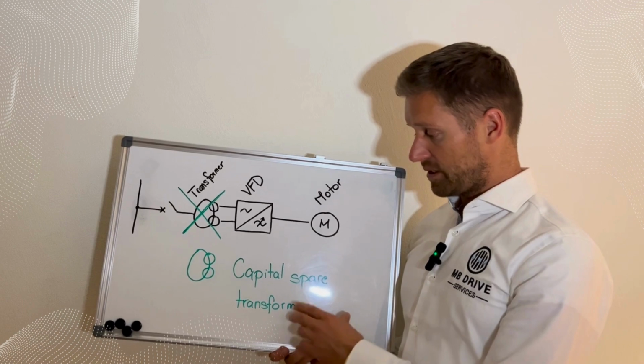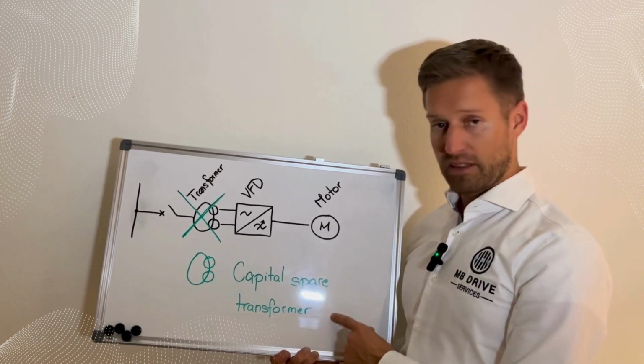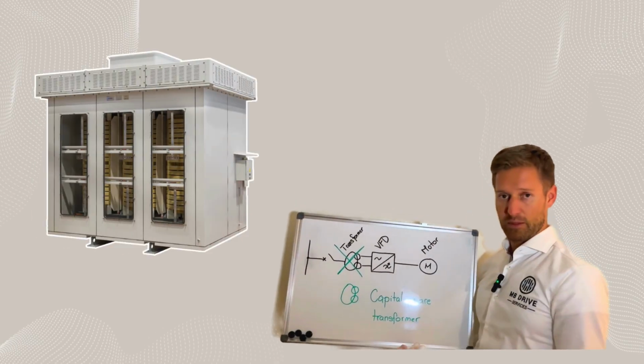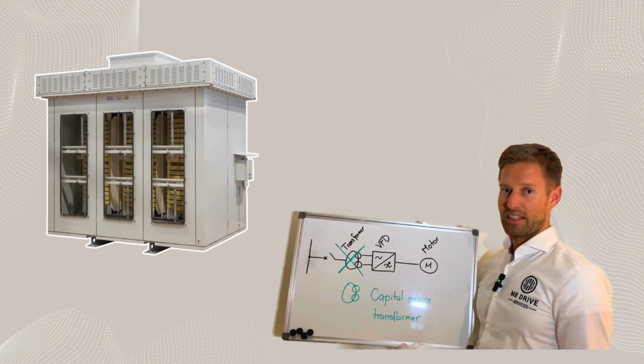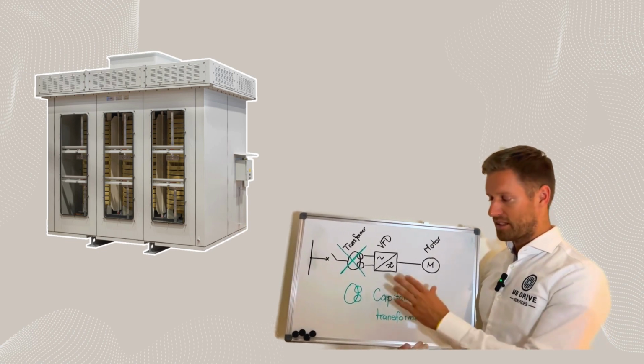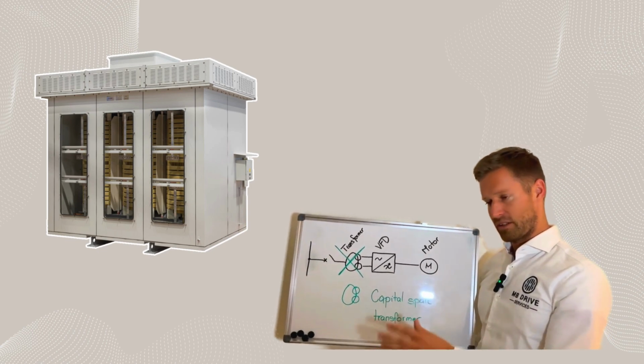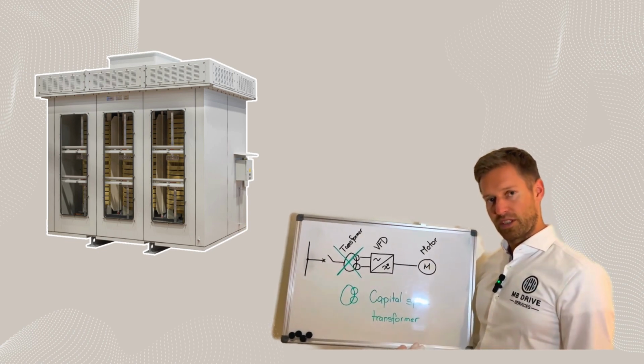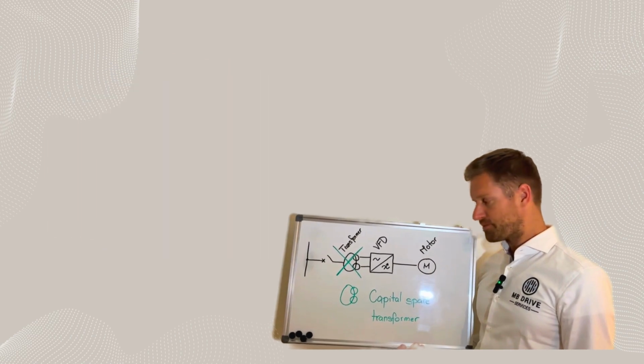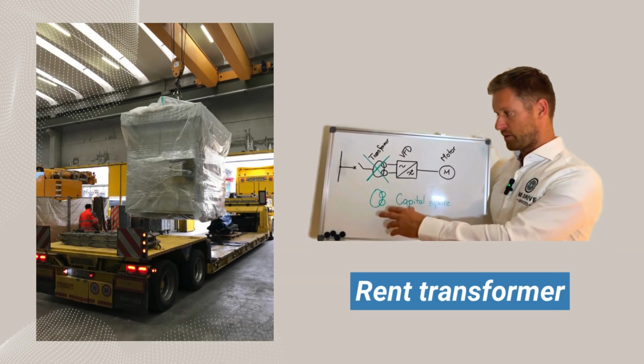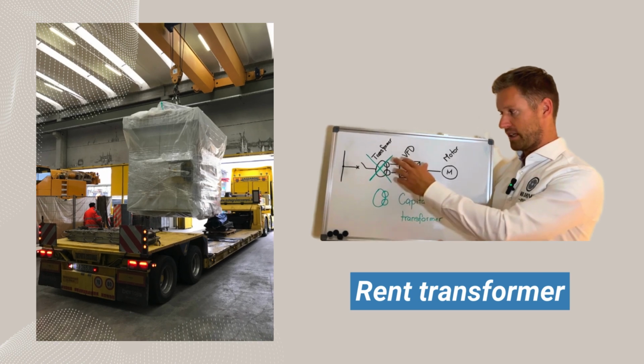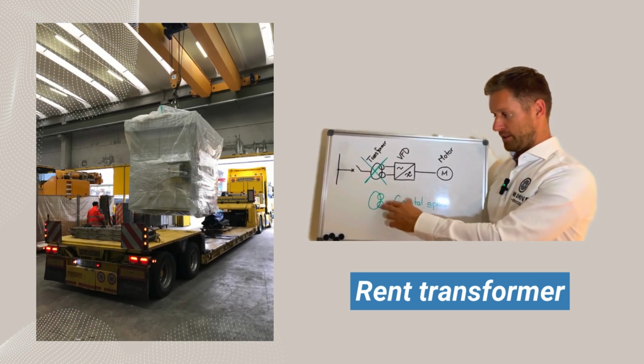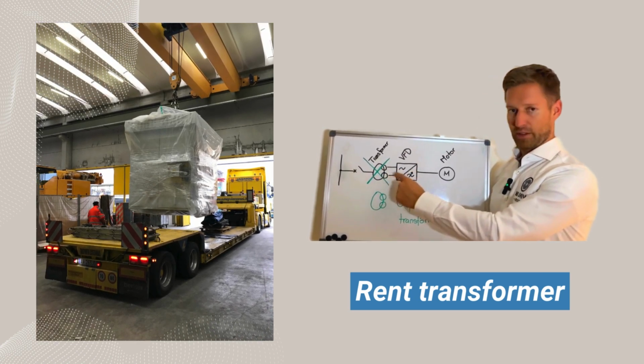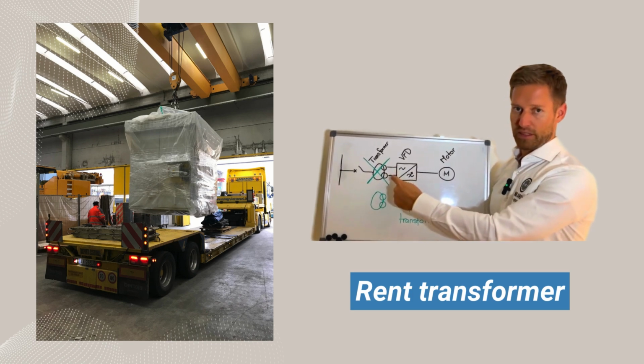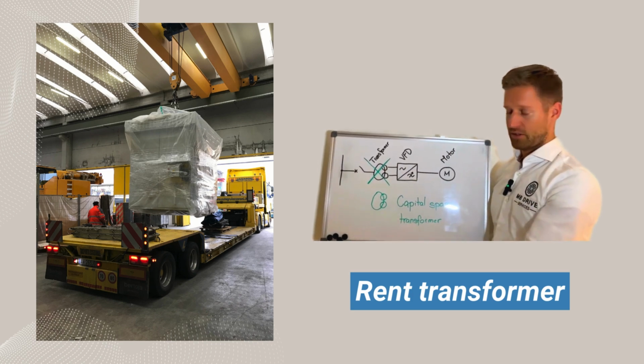To help the customers, we have our concept of capital spare transformer. So we have a transformer that is designed a little bit universally. It does not fit every VFD, but it's a little bit universal design to cover at least some portion of the installation in the field. And we can rent this transformer, and the purpose is to bridge the period until the original transformer is repaired or a new transformer is manufactured.